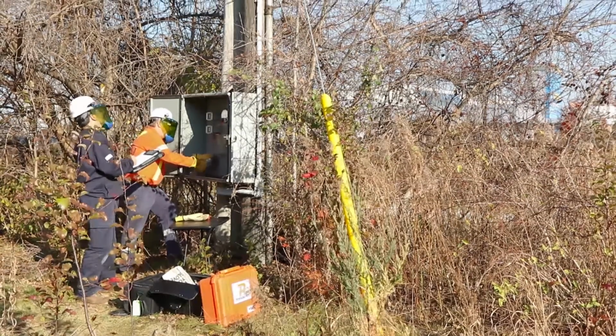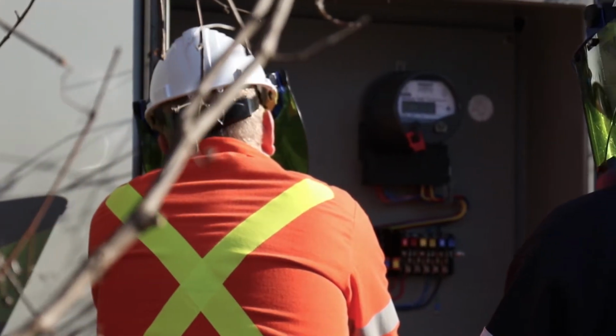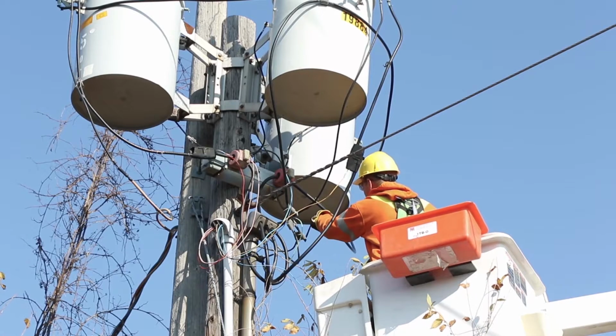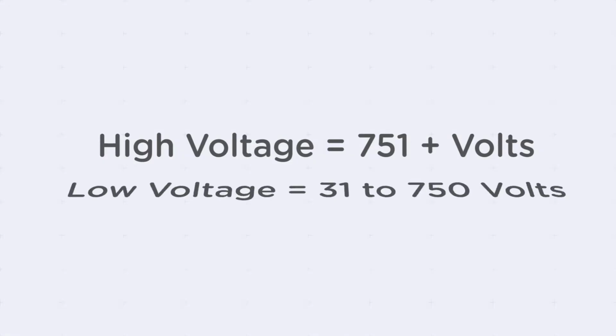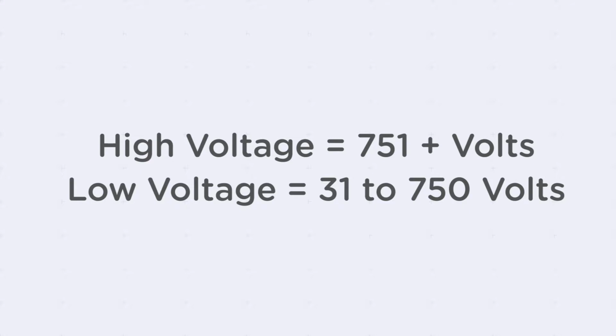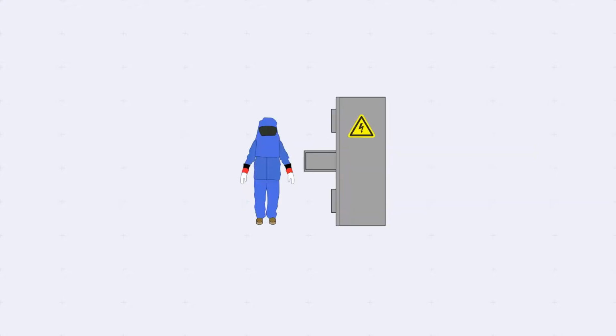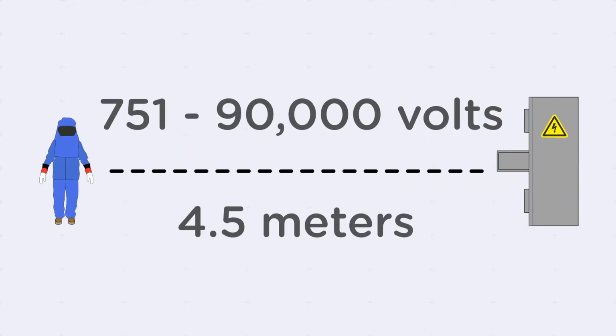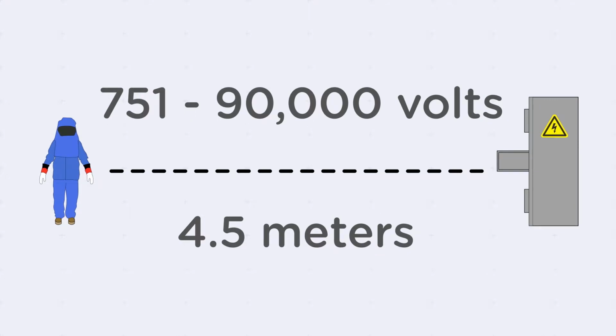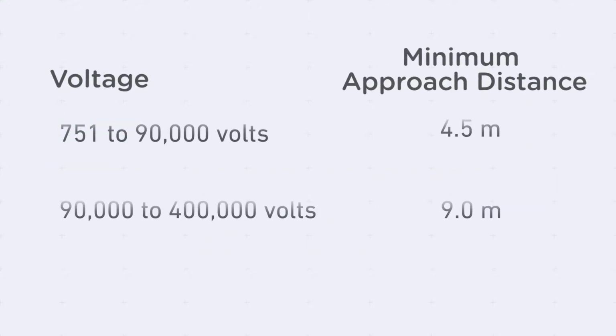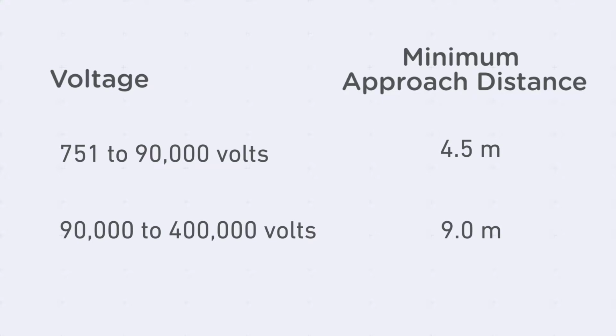Measurement Canada employees are qualified up to 750 volts. Based on the Canadian Electrical Code, high voltage is above 750 volts, and low voltage is between 31 and 750 volts. The minimum acceptable approach distance for metering installations with a voltage of 751 to 90,000 volts is 4.5 meters. For installations with a voltage of 90,000 to 400,000 volts, the minimum acceptable approach distance is 9 meters.